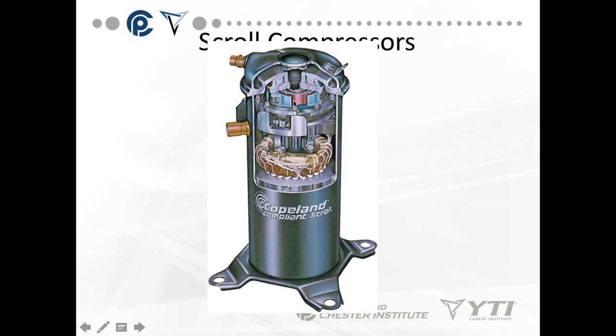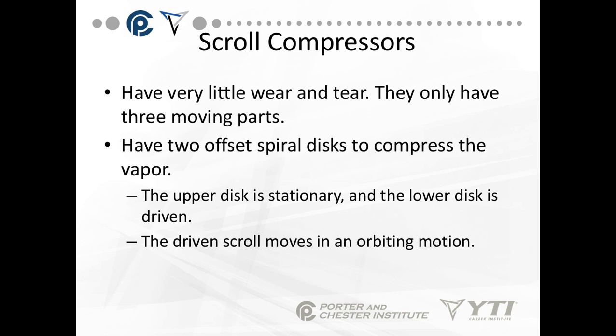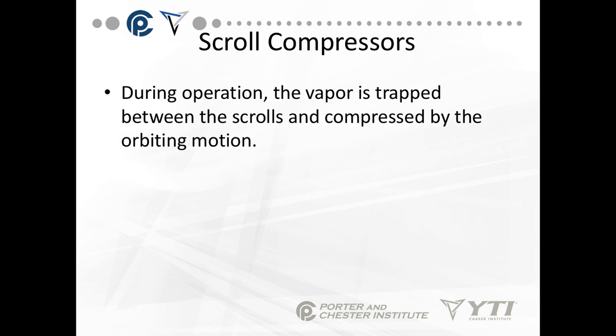You have a blue and red scroll. Those components rotate in more of an elliptical pattern back and forth, squeezing the refrigerant through the scroll until the high-pressure refrigerant comes out of the top. The scroll has very little wear and tear — it really only has three moving parts. The upper disc is stationary and the lower disc is driven. The driven scroll moves in an orbiting motion connected to an off-center or eccentric motor. During operation, the vapor is trapped between the scrolls and compressed by the orbiting motion.